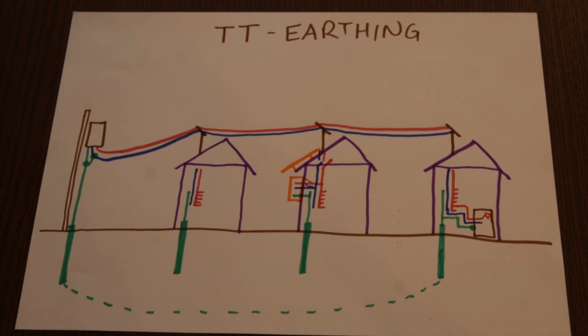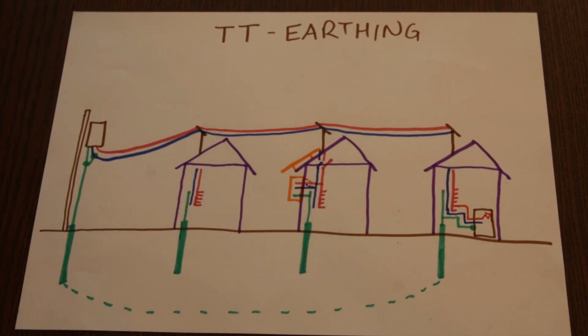So why do we actually even have to do this? This is because of requirements in such earthing systems. Because in the TT systems, I told you, we have rural areas. Usually the consumers are quite far away from each other, and they can be far away from the power source, which is the transformer. And all those impedances, resistances of these long distance wires, they're adding up, and the further away you are from the transformer, the requirements to trip your protective devices might not be fulfilled anymore, because those impedances will just be too high. So whenever those requirements cannot be fulfilled, the earthing system will be downgraded to a TT configuration, and RCDs have to be used.